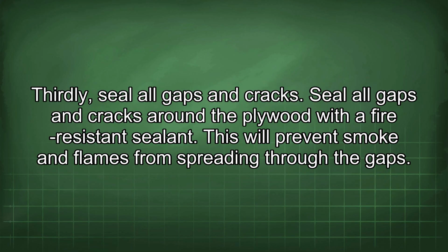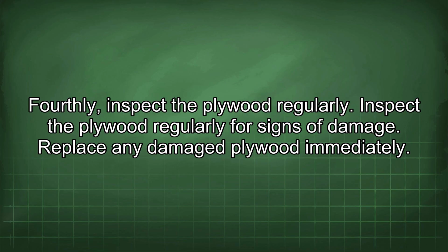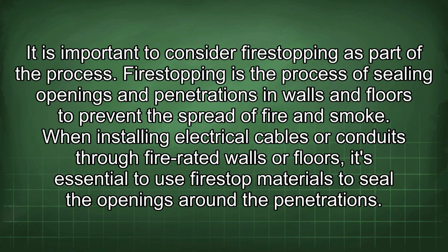Thirdly, seal all gaps and cracks. Seal all gaps and cracks around the plywood with a fire-resistant sealant. This will prevent smoke and flames from spreading through the gaps. Fourthly, inspect the plywood regularly. Inspect the plywood regularly for signs of damage. Replace any damaged plywood immediately. It is important to consider fire stopping as part of the process.